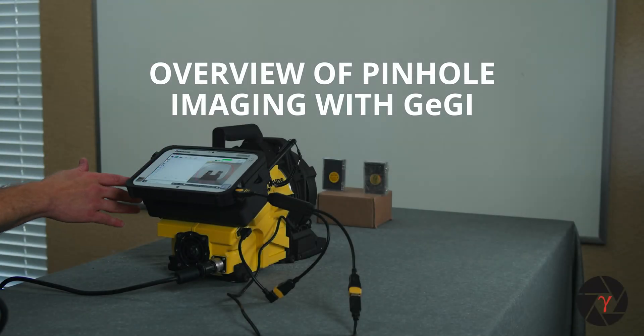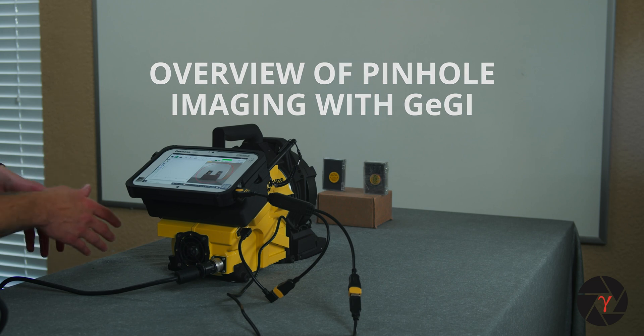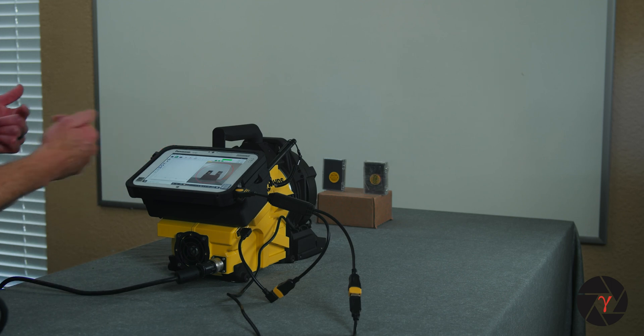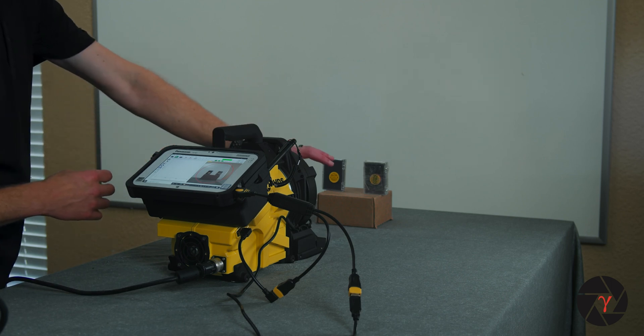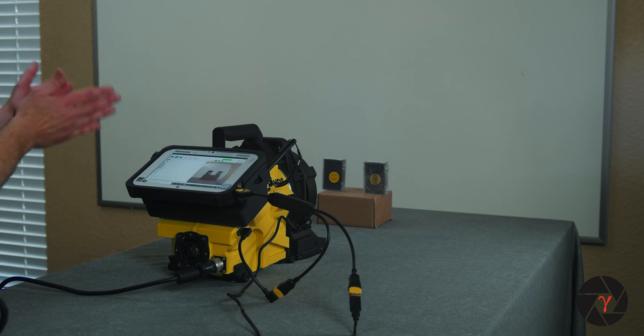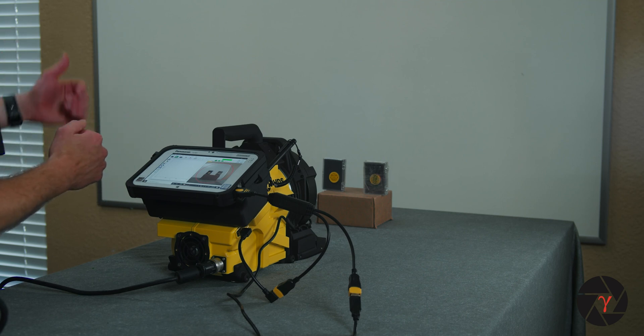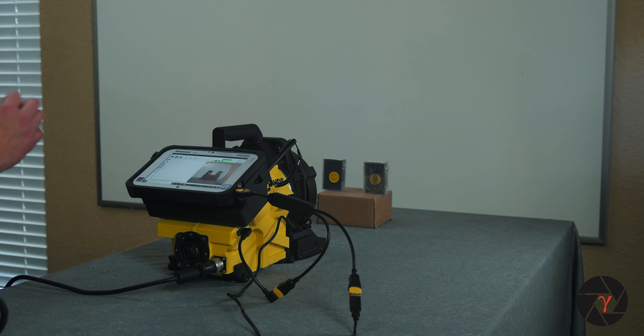Now for an overview of pinhole imaging with the GeGI. For pinhole imaging, you place a pinhole aperture over the front of the GeGI detector such that all of the gamma rays that make it through to the detector must pass through this 60 degree opening in the front of the pinhole shield. The benefit of pinhole imaging is that you can unambiguously separate multiple sources of the same isotope within the field of view. The drawback is that all counts have to pass through either a one, three, or five millimeter aperture, so the efficiency is much lower than Compton imaging, but the spatial resolution is far superior.